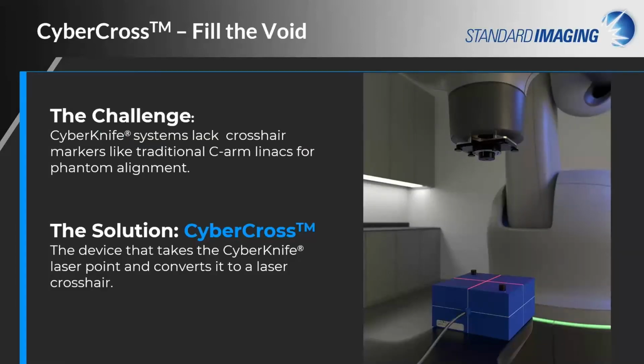What is that challenge? Well, as any CyberKnife users know, or potential customers know, the CyberKnife system is not equipped with a crosshair marker of any type, as the system uses fiducial skull and spine tracking for positioning. However, the system is equipped with an internal laser, which the CyberCross converts into a crosshair. CyberCross is simple to install and use to accurately position all types of QA equipment in the direct primary beam of the CyberKnife system.